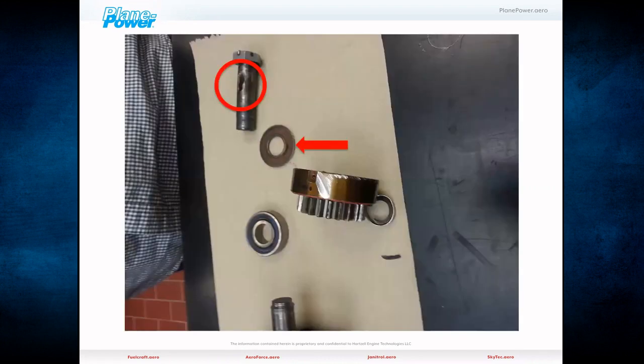So I look at the pieces, and I take these pieces. There's your rotor shaft. Now look at the circle, look at the woodruff key slot, look how worn out it is. That tells me that gear coupling, right in the middle of the page, has been banging around on that shaft, which tells me the gear coupling was loose. At every power point, every power surge of the engine, every change in electrical demand, boom, boom, boom, it was pounding back and forth on that slot because that coupling was loose.